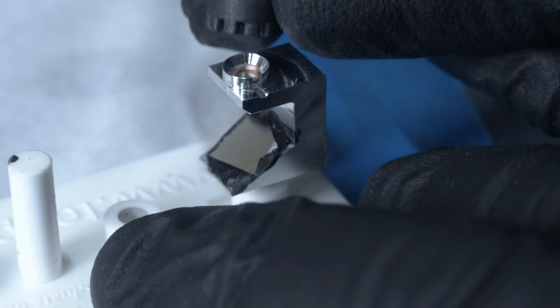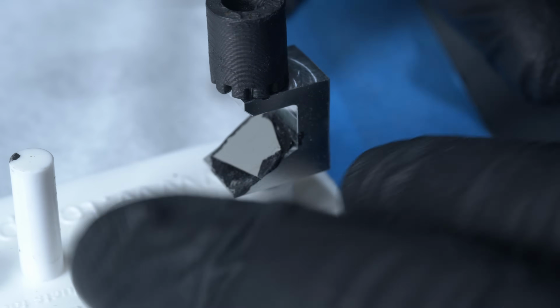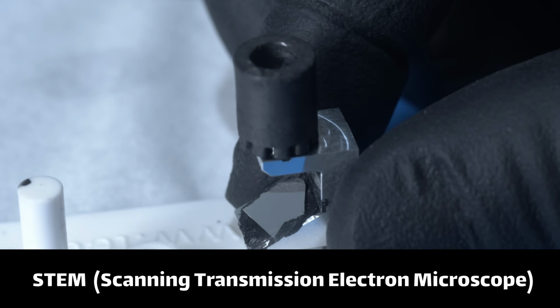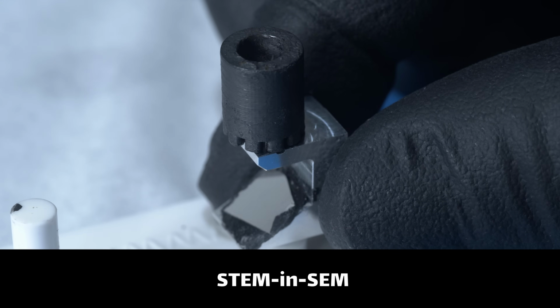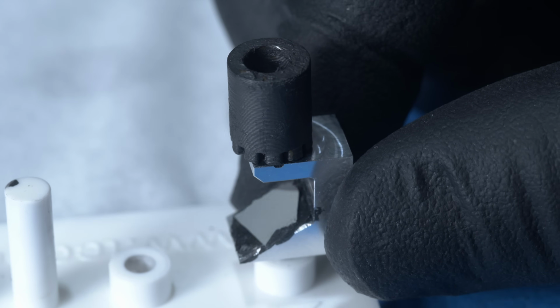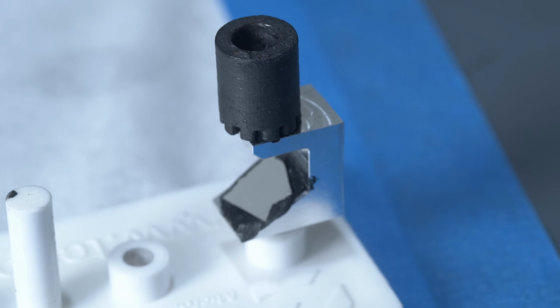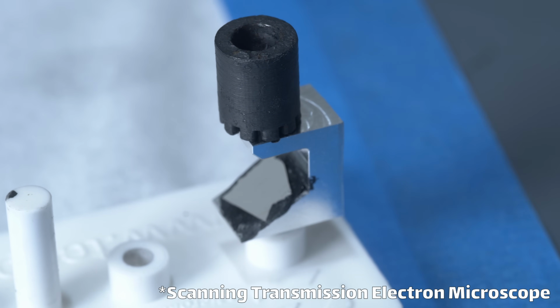So that brings us to this little device that I made. This is known as a STEM conversion device, or a STEM-in-SEM. And basically it turns your scanning electron microscope into a transmission electron microscope. And the mechanism to do this is pretty clever in my opinion. The device is structured with an angled metal plate at the bottom and then a small sample cup at the top, which holds our very thin sample. And that's basically it.